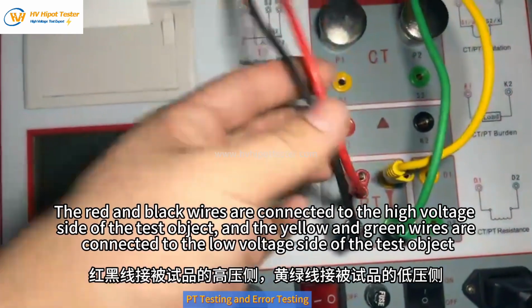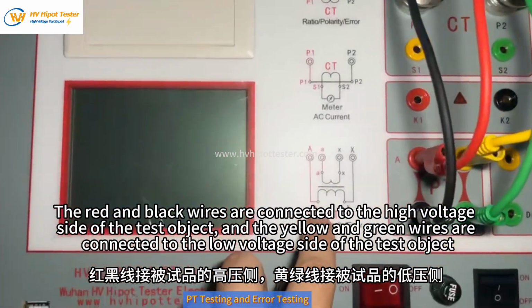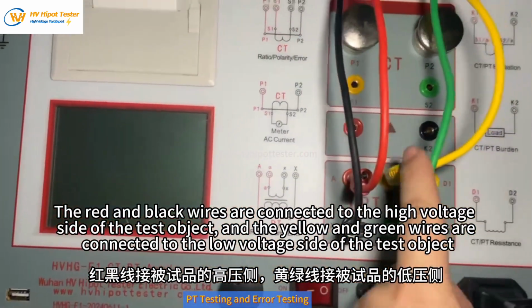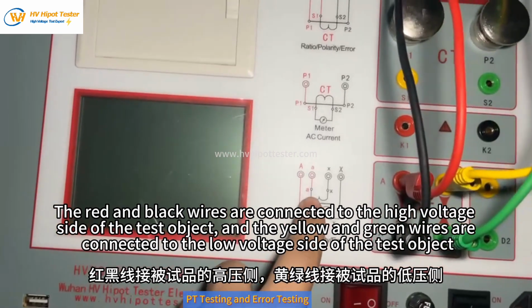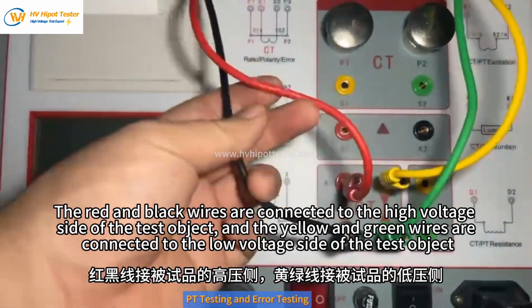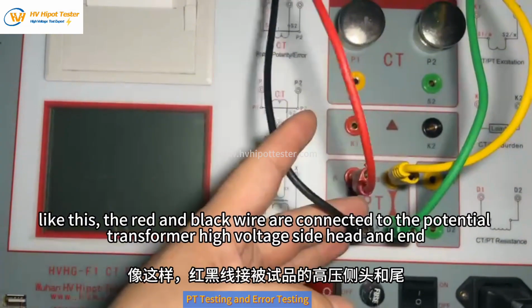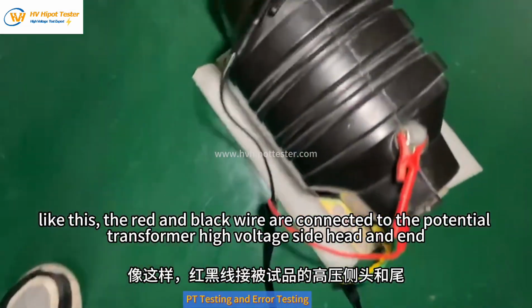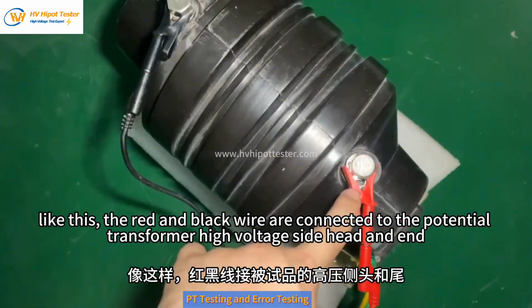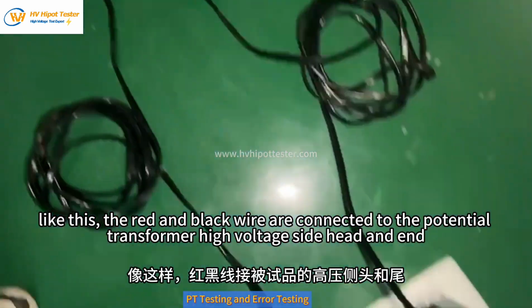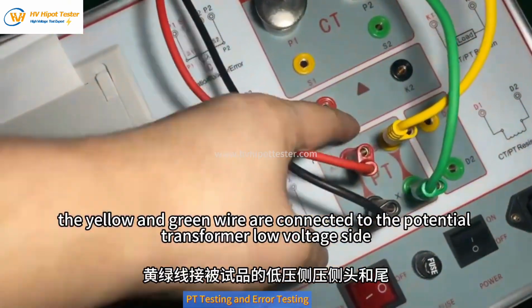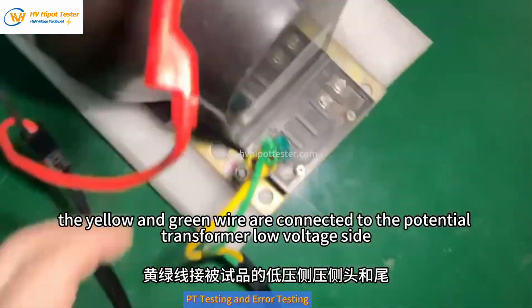The red and black wires are connected to the high voltage side of the test object, and the yellow and green wires are connected to the low voltage side of the test object. Like this, the red and black wires are connected to the potential transformer high voltage side head and end. The yellow and green wires are connected to the potential transformer low voltage side.